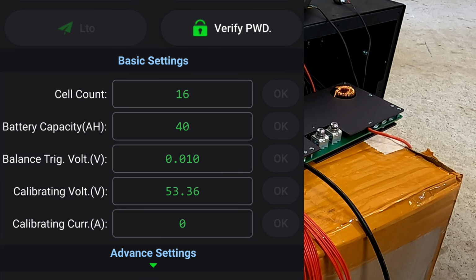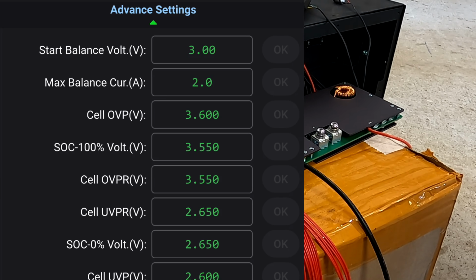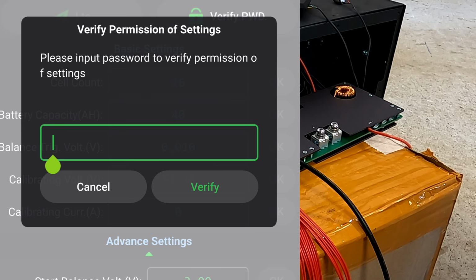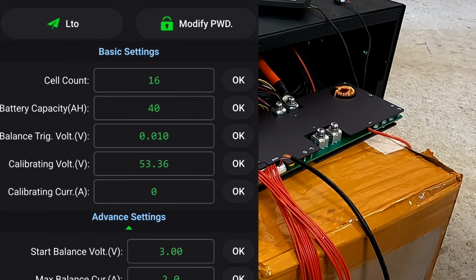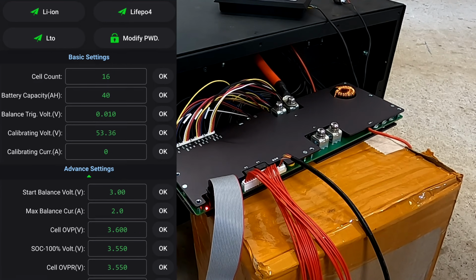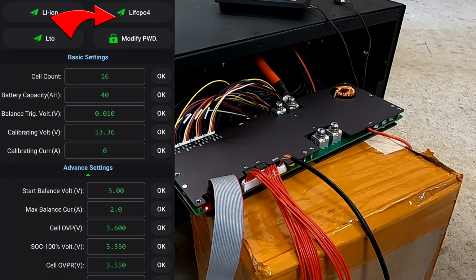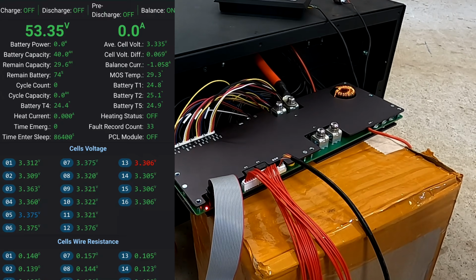Clicking on the advanced settings, I'll put in my password and verify. First we should click on the lithium iron phosphate profile at the top, and you'll see some of the figures down here change accordingly. You should only click this button once at the very beginning, because once you start modifying parameters and click it again, it resets everything back to the default settings of that profile. Let's have a look if it's still balancing - yeah, the balancer is still active.